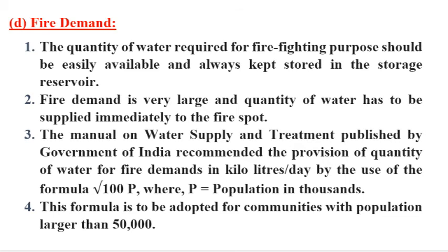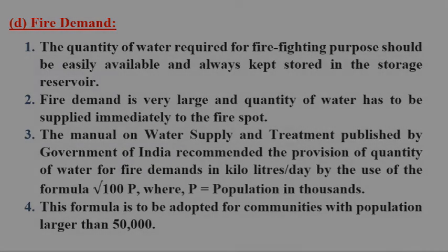The Manual on Water Supply and Treatment published by the Government of India recommended the provision of quantity of water for fire demands in kiloliters per day by the use of the formula under root 100p, where p is population in 1000. This formula is to be adopted for communities with population larger than 50,000.